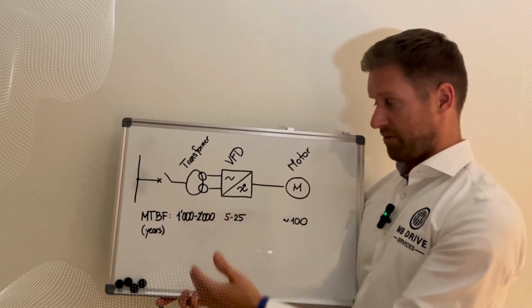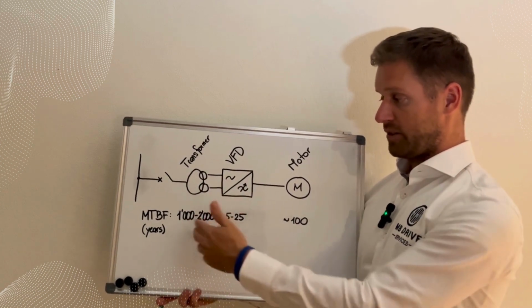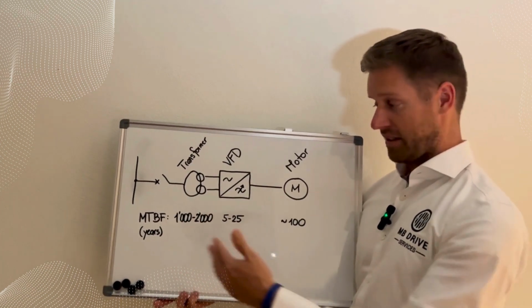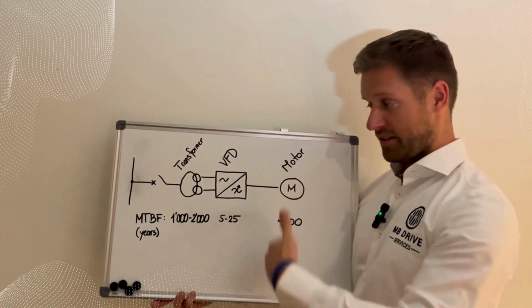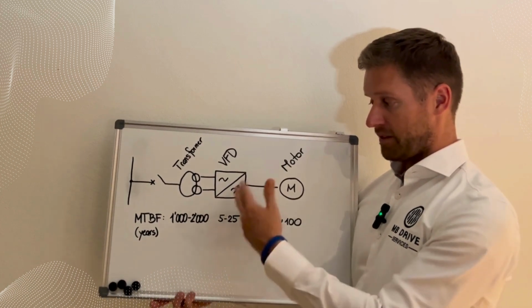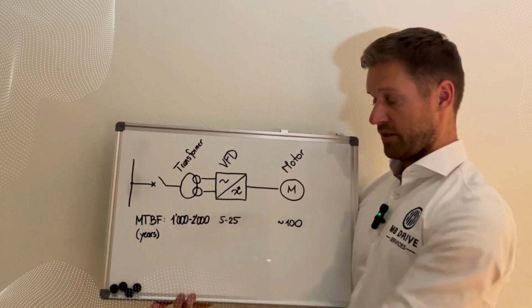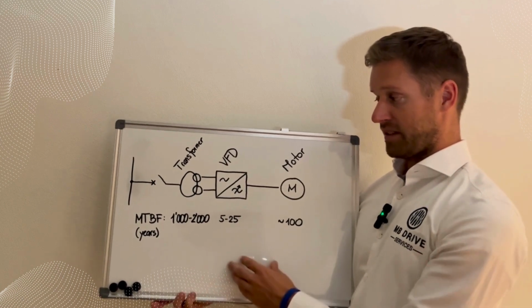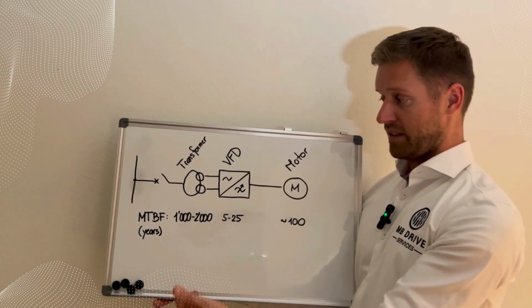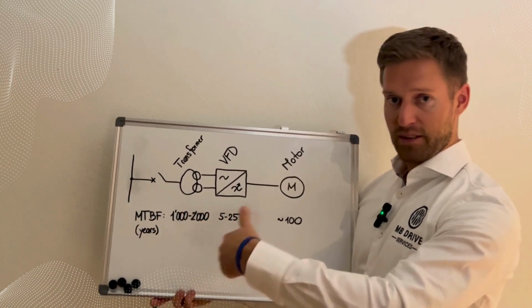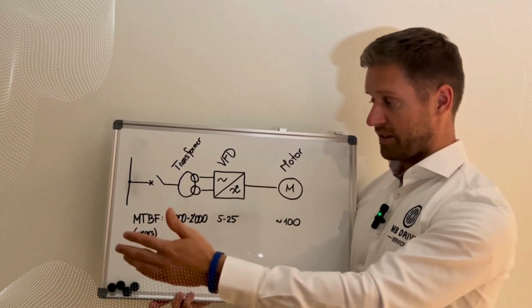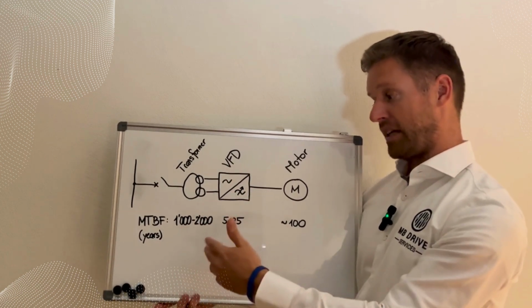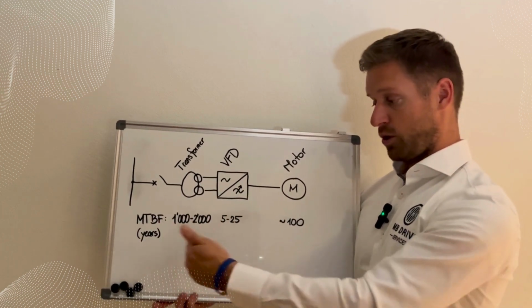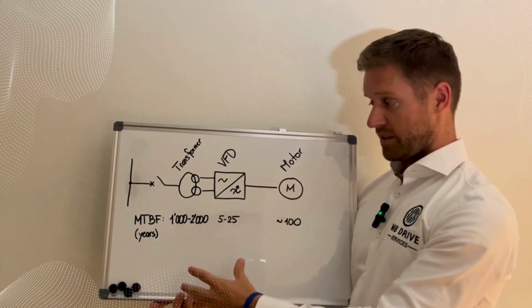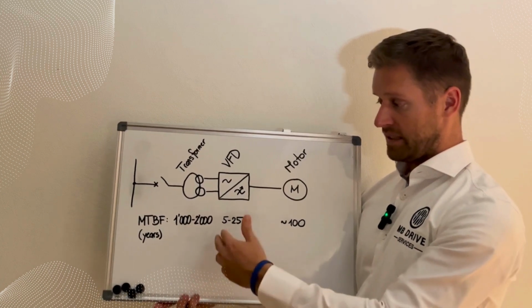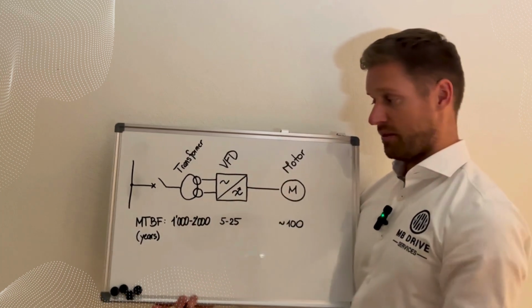and some of them fail. Combined, you get this statistic: the total operating time, in operating hours or operating years, divided by the number of failures, gives you the MTBF. So if you have 100 transformers installed in the field and 99 of them work throughout their whole lifetime without any failure, and one fails, then you take the cumulative operating hours of all 100 transformers, and this will be the MTBF because you just have one failure.